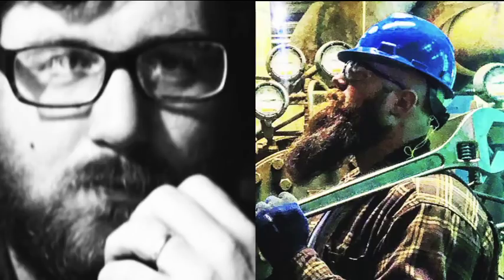And that's pretty normal for a screw compressor. So that didn't alarm me too much. But what we had was like a 21, 22 degree temperature difference across the condensing barrel. And that's alarming. So we know if we have an increased temperature drop across a barrel like that, it's going to suggest to us water flow issues. So the first thing most of the time with a chiller system is you'll check your pumps. They usually have strainers in them, or you'll have a Y strainer somewhere near it. Your cooling tower, which is another point where you can get obstructions that could cause water flow issues. And then the chiller itself, your barrel could get the tubes plugged up. That's a lot less likely to cause that big of a pressure and temperature drop, but it is a possibility.